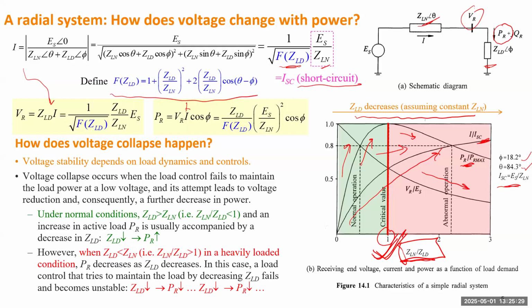Okay, but what this figure tells us is that the method of decreasing the impedance to maintain the power can be successful if you operate in this green zone. But in the red zone, it totally fails. But the controller doesn't know. The controller just keeps doing it until it pushes the system to collapse. All right. But in order to know when you move to the right zone, you need to have the whole picture of the entire system, or at least the majority of the region involved in this event, not just this single load.